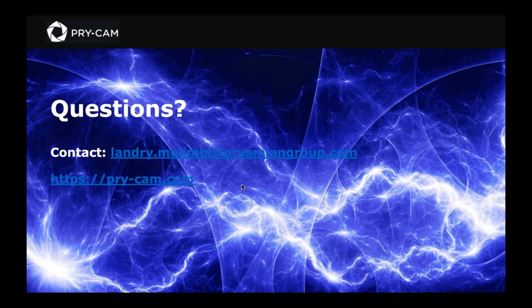It depends again on the cable system environment and the DAS technology we use, so there's no straight or concrete answer. However, when using DAS for underground and submarine cables, we mainly look at cable faults, anchoring, digging, and manhole cover opening. When it comes to cable faults, I'd say the precision is excellent—DAS allows us to precisely detect and locate a fault.